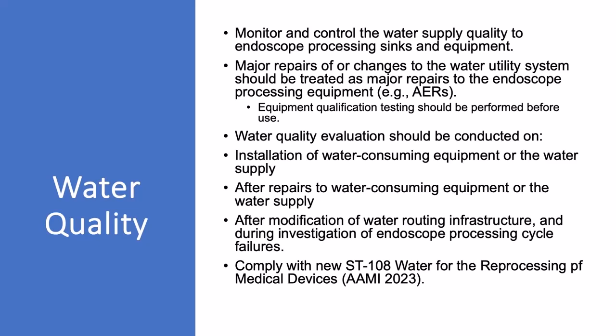And your equipment should be requalified before use if you have a major repair to your water. Water quality evaluation should be conducted when there is installation of water-consuming equipment or the water supply, after repairs to water-consuming equipment or the water supply, so say you have a water main break outside your facility, after modification of water routing infrastructure, and during investigation of endoscope processing cycle failures, and comply with the new ST108, water for the reprocessing of medical devices, that was just published from AAMI.